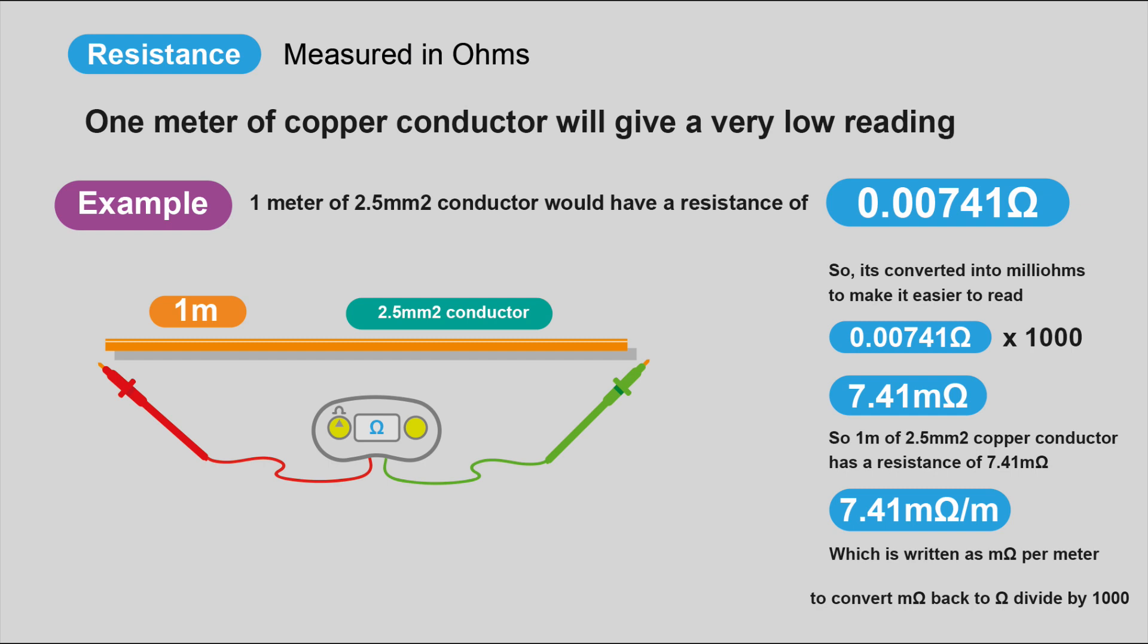We're only going to deal with copper conductors here. It's such a good conductor that the values we're talking about, the numbers we're talking about, are very, very low. In this example here, we've got one meter of 2.5 millimeters squared conductor, and that would have a resistance of 0.00741 ohms.